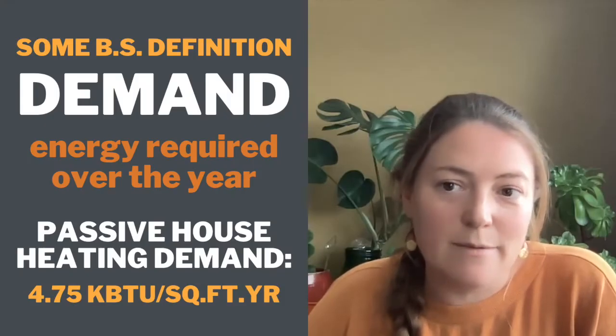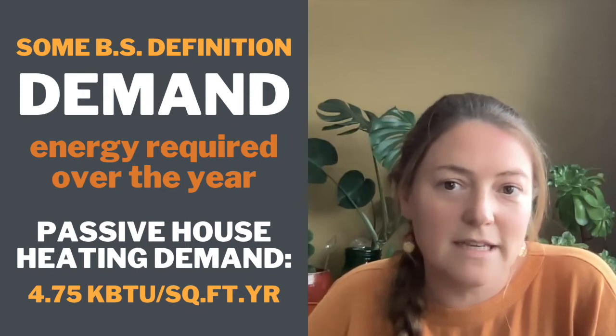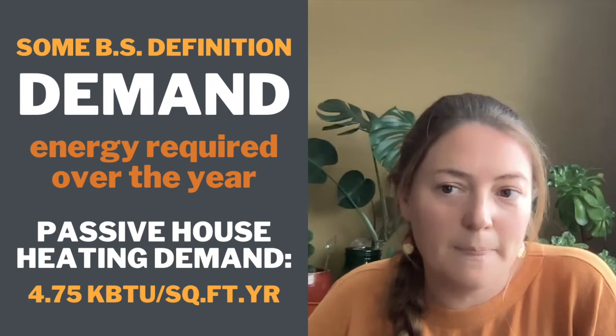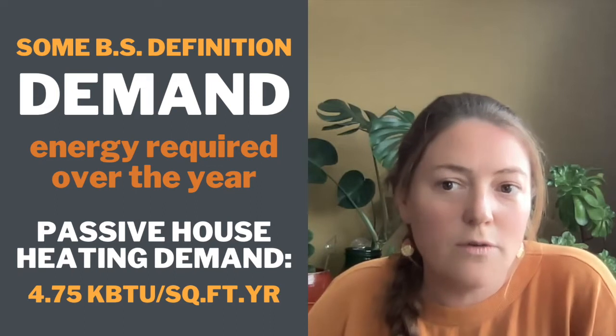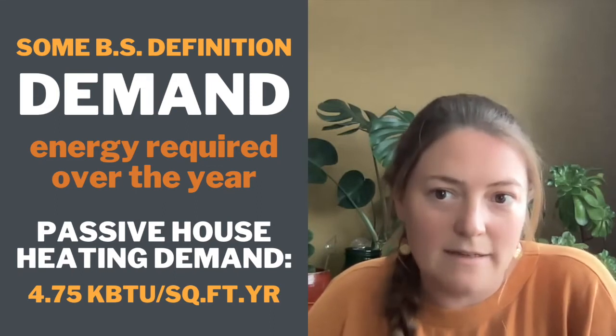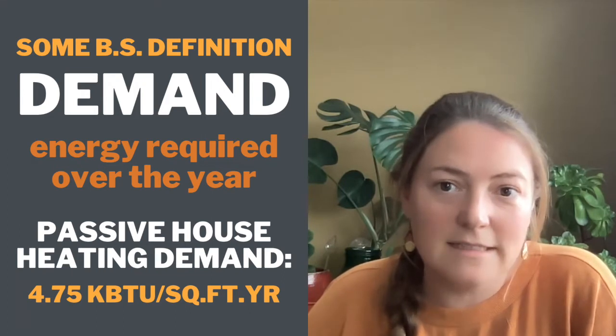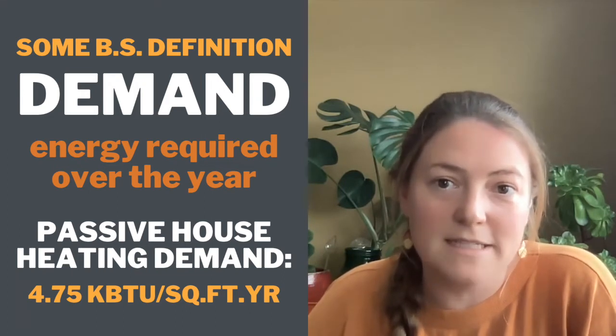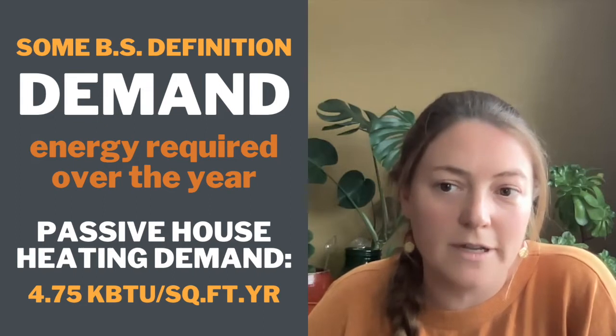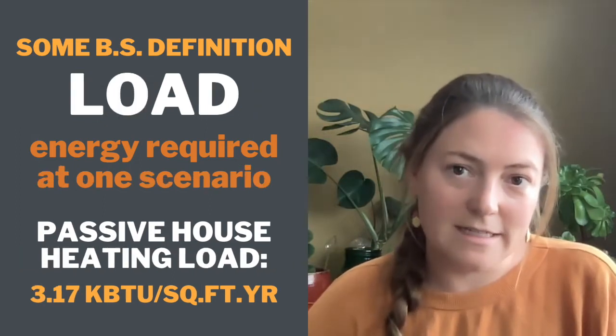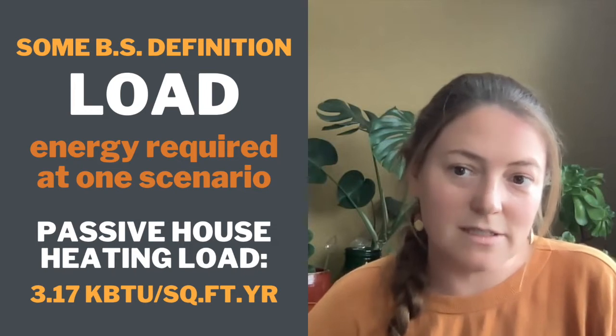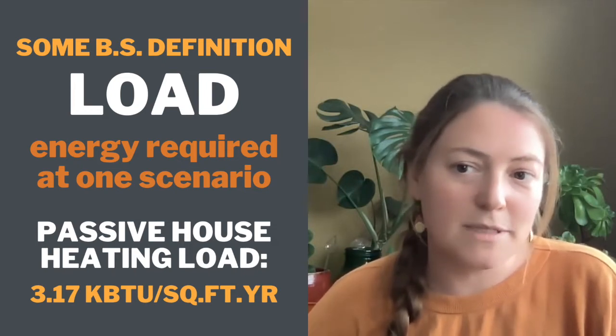The energy demand is the amount of energy that a specific service of the building requires over a typical year. So for example, the heating demand is the energy that the building consumes over a year for the heating to be supplied. In a Passive House, that heating demand is capped at 4.75 kBTU per square foot per year. The energy load, on the other hand, is the maximum amount of energy needed for that building service to provide comfort at a particular worst case scenario. So again, demand is over the entire year and load is in a specific scenario.